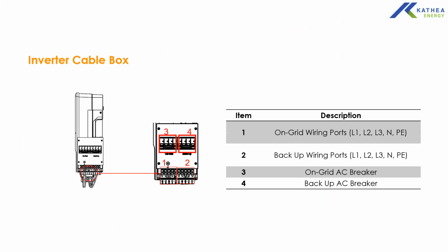With this three-phase system, please note it's sensitive to phase rotation. So make sure your phases are wired correctly, the standard being red, yellow or white, blue. So make sure they follow that sequence. If not, upon power up, the system would give a phase angle error. Then you would need to swap around to make sure you get the correct phase angle. And then for the loads, it's a three-phase. You can wire them to three-phase loads, or you can supply single-phase loads. That is each phase considered as a single phase against neutral.